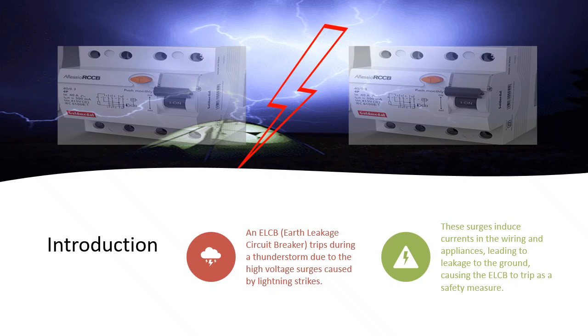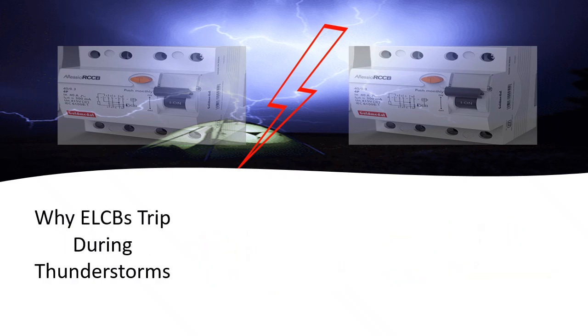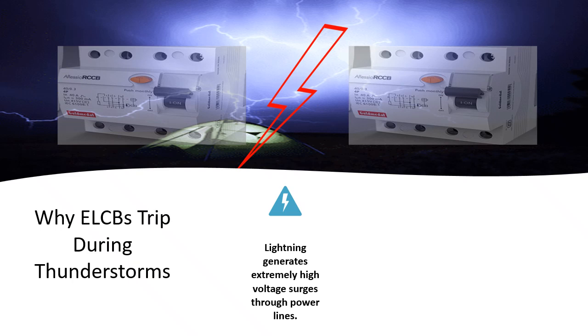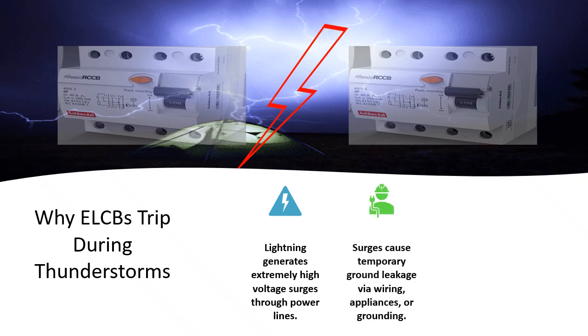Why do ELCBs trip during thunderstorms? Let's understand the causes in detail. Lightning generates extremely high voltage surges that can enter through power lines. These surges often cause temporary ground leakage through faulty wiring, appliances, or even the earthing system. Since ELCBs are very sensitive, even small leakage currents are enough to trigger a trip and disconnect the power.